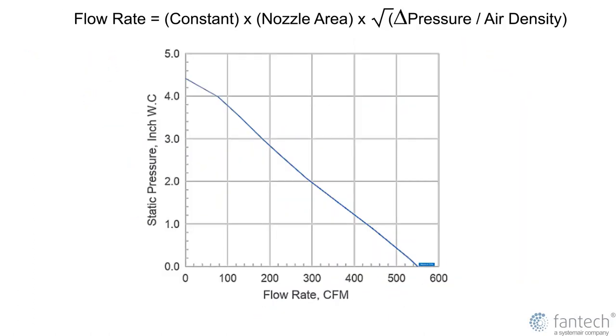Flow rate can be calculated from pressure drop across the nozzle wall, air density, and total cross-sectional area of all open nozzles.